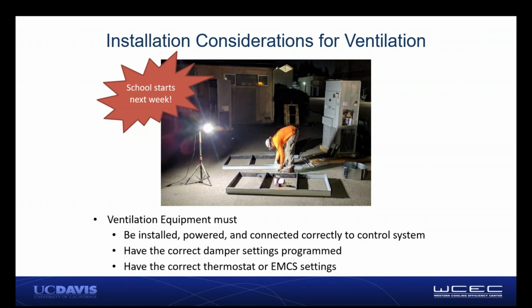You've got to get heating and cooling working because students need to be able to go to school. So you get the system up, but the question is, in order for the ventilation to work, it has to be installed, powered, and connected correctly to the control system. It has to have the correct damper settings, programs, and the right settings in your EMCS. So there are a whole bunch of steps past the fact that the heating and cooling is working. That's really what schools are up against. There's a lot of work that has to happen after that system gets put on the building.